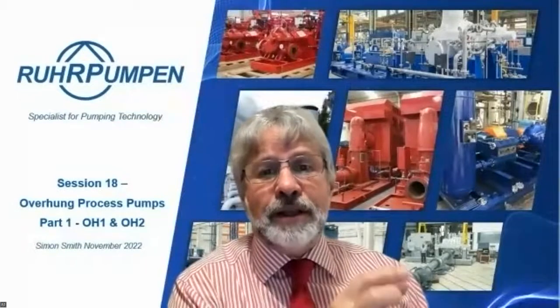Anonymous attendee says, why does API 610 specify minimum impeller wearing clearance and not the maximum impeller wearing clearances? Okay, I've got it. Why it does that is to ensure that you don't use tighter wearing clearances to increase the efficiency of the pump, which it will do for sure. But it says that's taking advantage. You need to keep this minimum clearance to ensure good operation of the pump. It will wear with time, and those clearances will open up and the efficiency will drop off, and you should be monitoring that to know when you need to overhaul the pump. But the minimum is just to make sure that you're not taking advantage of using closer running tolerances to get improved efficiency unfairly.